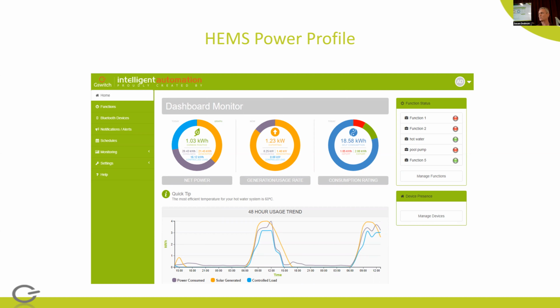Susan, do you have anything else? Can I just add something, Rob? On the back of that, the HEM systems can be notified that the diesel has started, and for those that can slow down their loads - if everyone wants to slow down their loads, they can actually shut that diesel generator down. So as long as we can see the signals and the network's talking, we may be able to slow down the air conditioners to 50% to stop that diesel generator from firing.